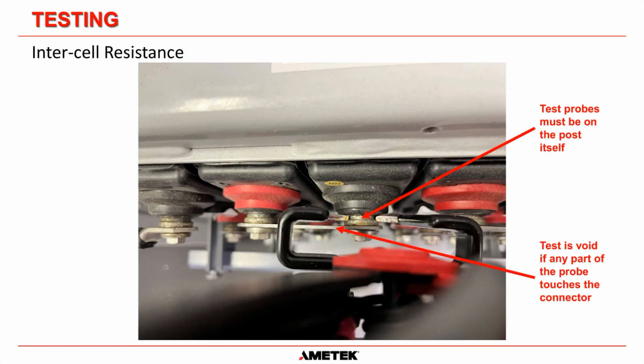That is why it is critically important, when either your plant staff or you yourself as a battery tester is going out to do the test, that you ensure the probes do not touch the intercell connector, or the test is void. The test is only measuring the resistance of the strap, and the strap is the strap. It shouldn't degrade anyway. We want to measure the connection between the battery and the strap and then back to the battery again. I hope that makes sense.